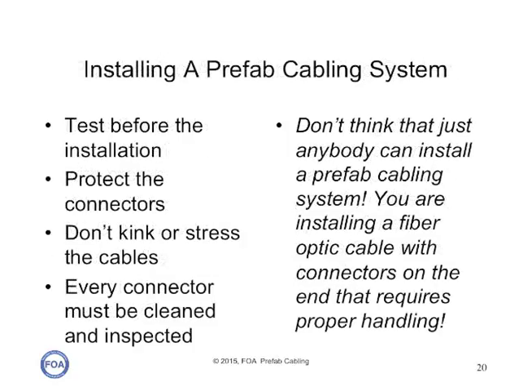It sounds like installing a prefab system should be easy, right? No splicing, no termination. But you've got to test it to make sure that as it's delivered to your facility, it meets its spec and it has not been damaged in transit. You need to make sure that all the connectors are cleaned and protected, that during the installation you don't kink or stress the cables, and that every time you do a connection, you clean and inspect the connector, because the MPO connectors have large ferrules and are particularly susceptible to contamination and dirt.